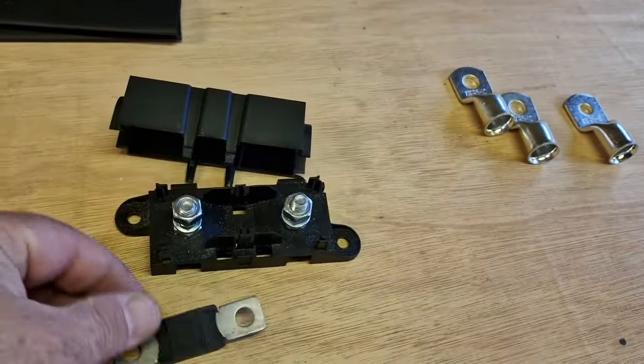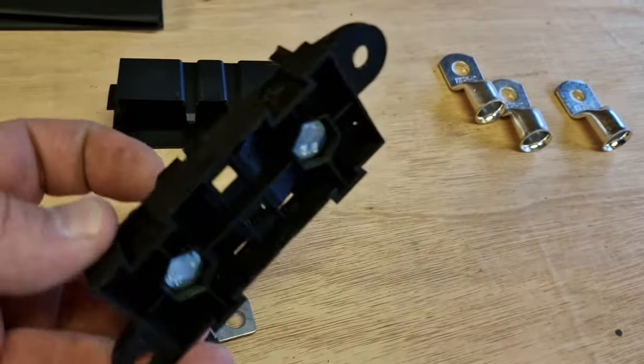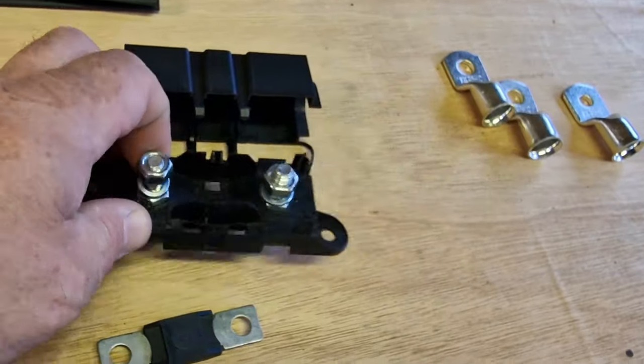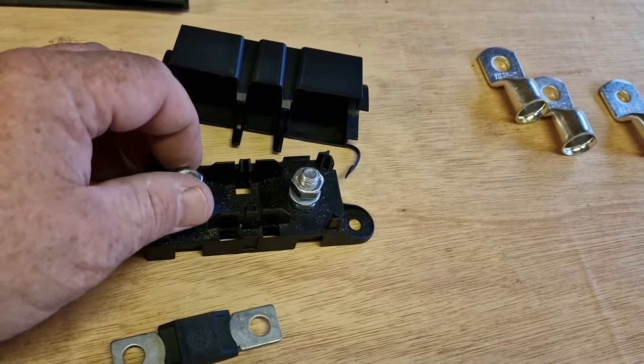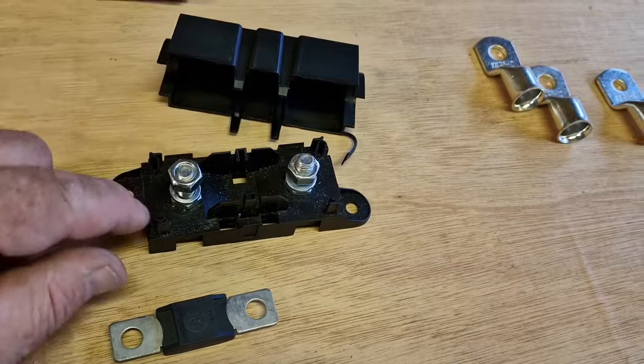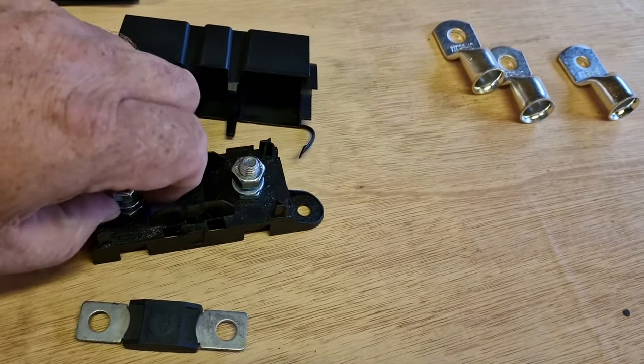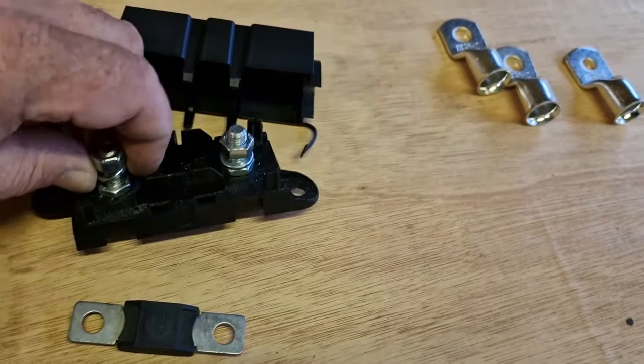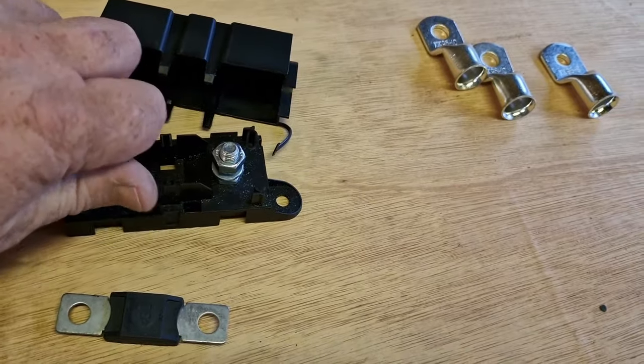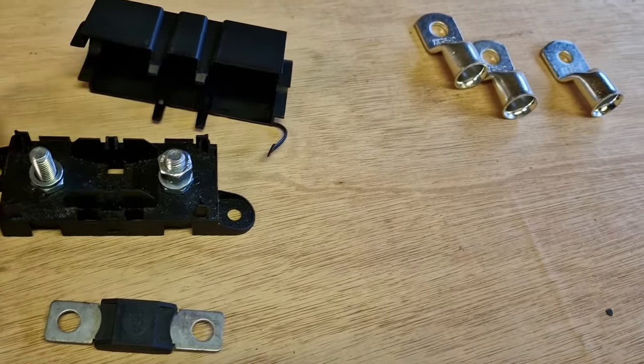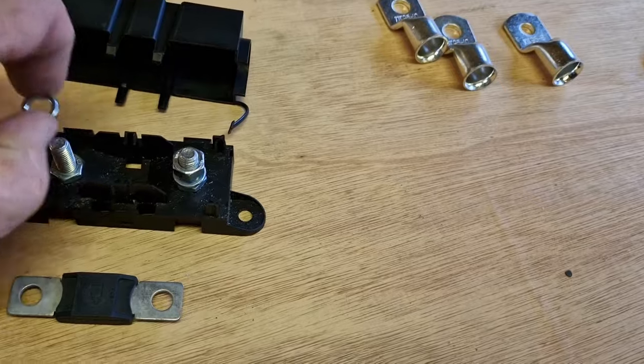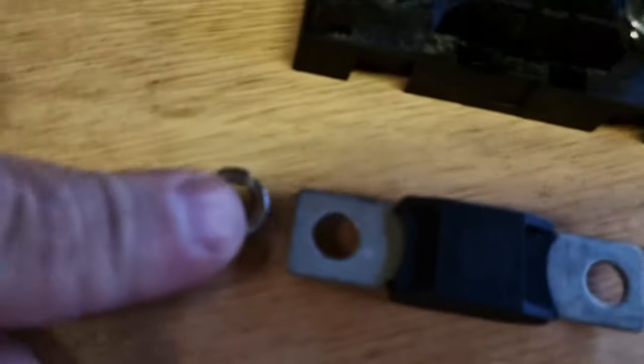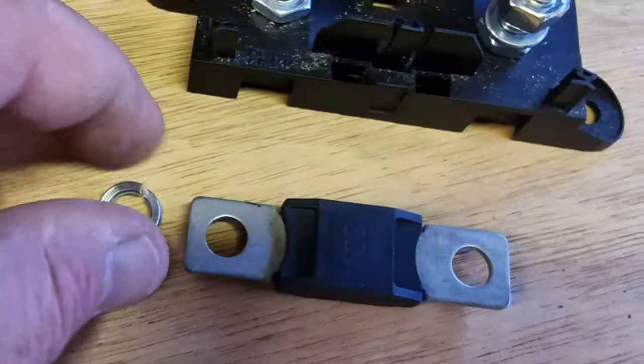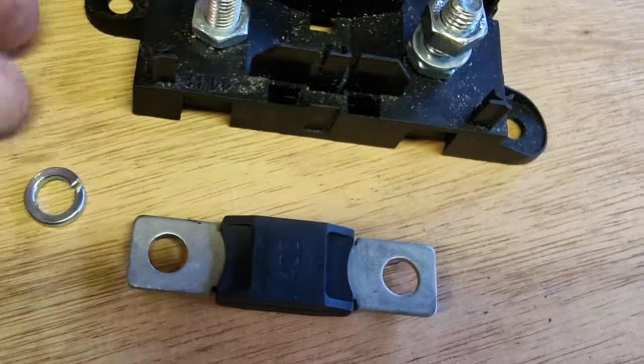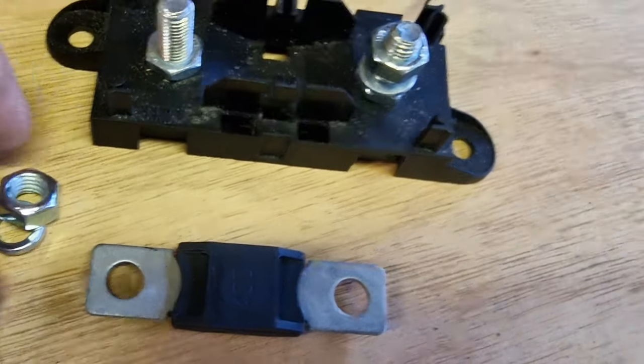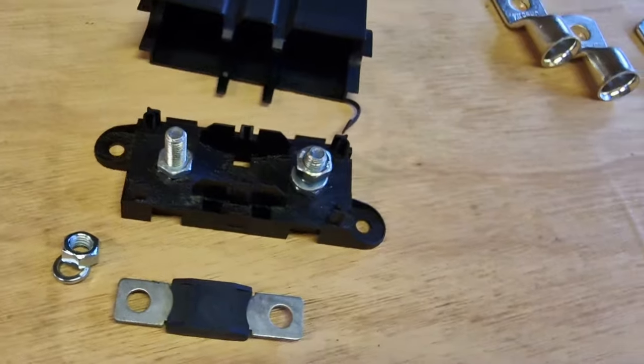Mega fuse holder with split washers, and that's for anti-vibration. So when we put the fuse on the bottom, up against that nut, split washer on top, and then we screw the nut down, and the nut basically will bite onto that split washer. I don't know if you can see that, and compress it, and that will stop them from vibrating loose.